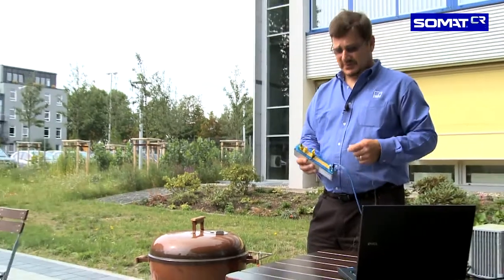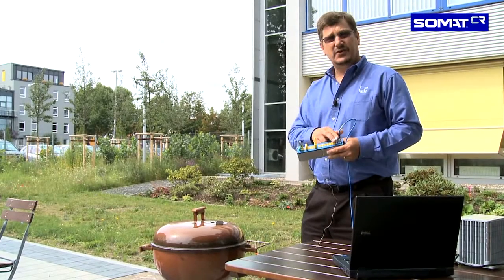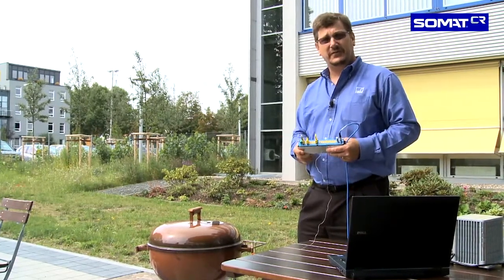The SOMAT-CR is the first in a new range of products from HBM designed to work with CAN interfaces. This thermocouple unit can carry 16 thermocouples, this type K. T's and J's are also available. This device can be daisy chained into a system with up to 15 of these into the eDAQ, so you could have 250 plus channels per CAN interface.